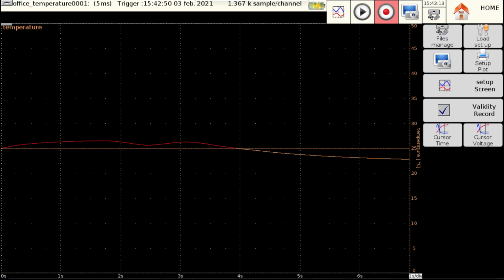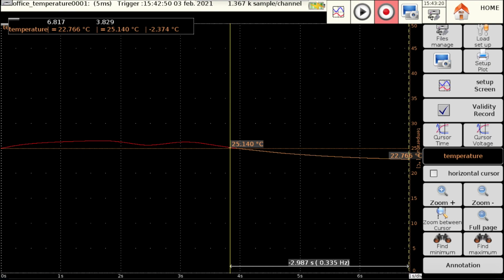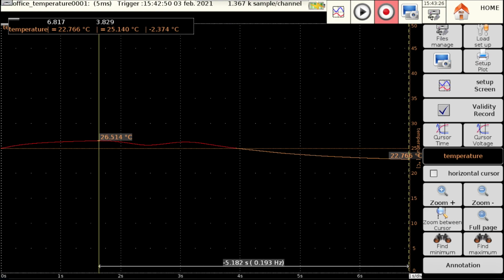We can analyze this recording directly on the device, for example by setting cursor time. With these cursors, we can also search for the maximum and minimum point of the recording. In our case, the maximum temperature is 26.5 and the minimum temperature is 22.7.